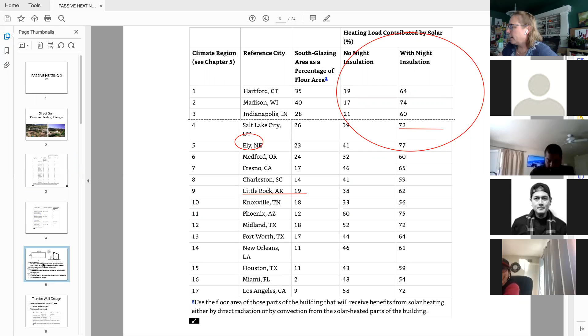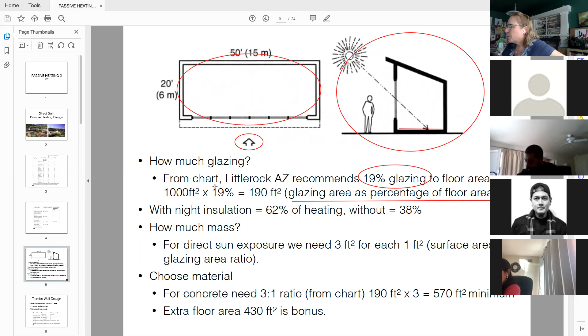So we go back to our chart with our different climate conditions, and for Little Rock, Arkansas, rule of thumb guidance is 19% of your floor area is needed for a direct gain passive heating system. So 19% glazing. And again, this is a percentage of the floor area. So it's based on the total square footage of the building, the room, whatever your design is. Okay, so 1,000 square feet at 19% is 190 square feet of glazing directly facing south.